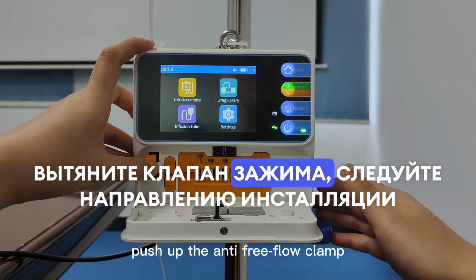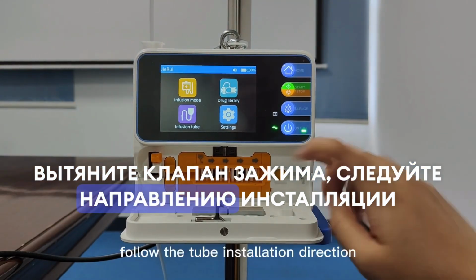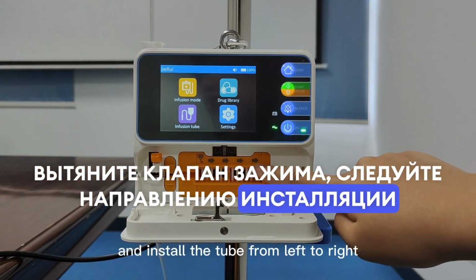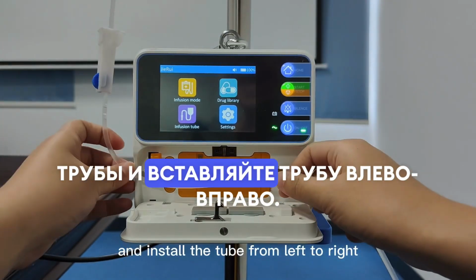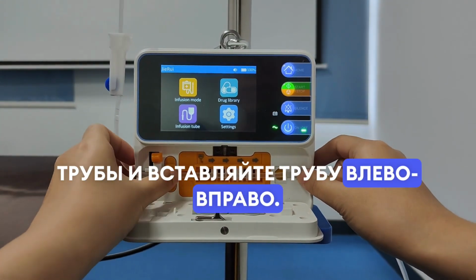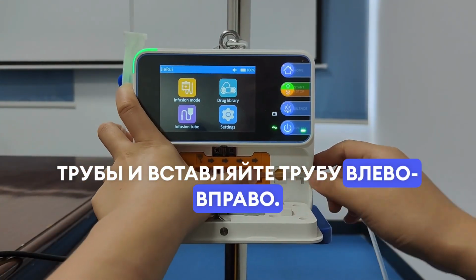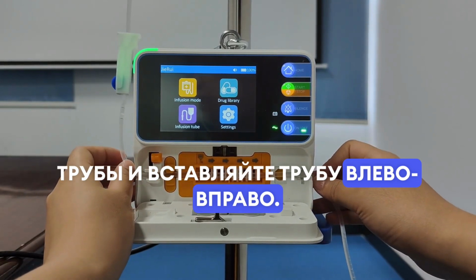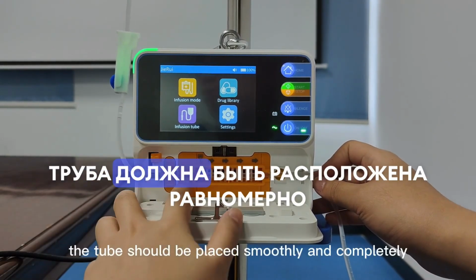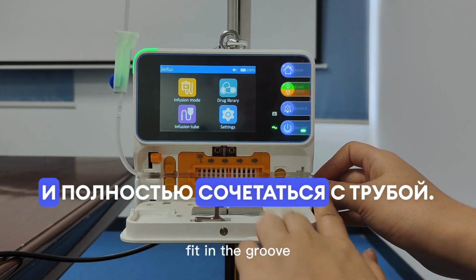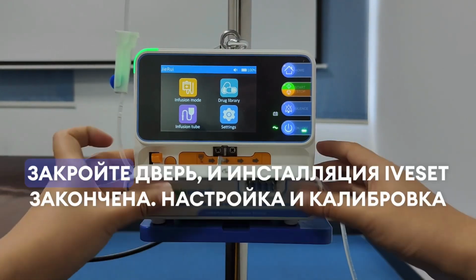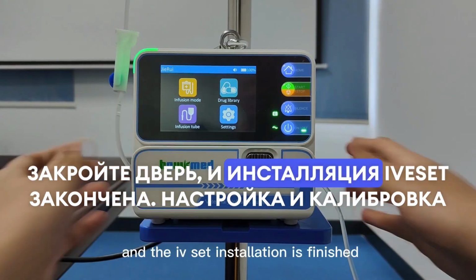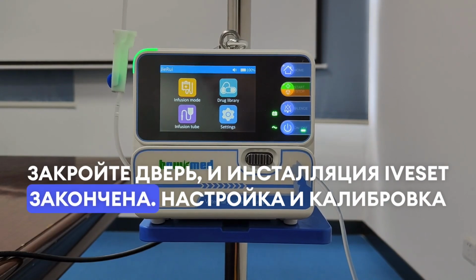Push up the anti free-flow clamp. Follow the tube installation direction and install the tube from left to right. The tube should be placed smoothly and completely fit in the groove. Close the door and the IV set installation is finished.